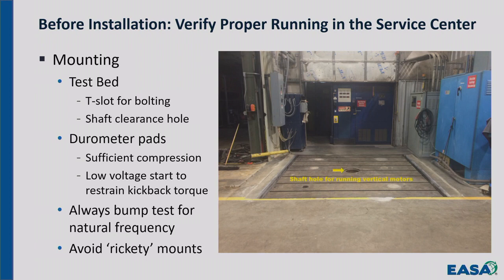That is not the frequency of that motor installed on the pump. When it's installed on the pump, it'll have a completely different frequency. So there's confusion sometimes. The motor manufacturer says the reed natural frequency is 4,000 cycles per minute, and it's a 1,800 RPM motor. I shouldn't have any problem. That's not true. That's the motor bolted solid on a test bed. You take that same motor and you bolt it on top of a pump. It has a completely different and much lower natural frequency.